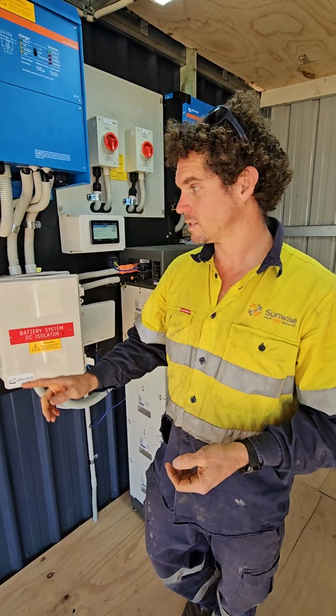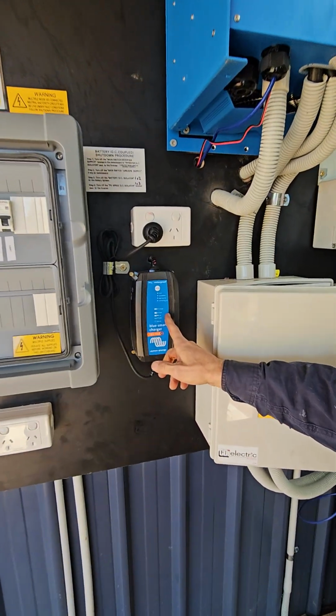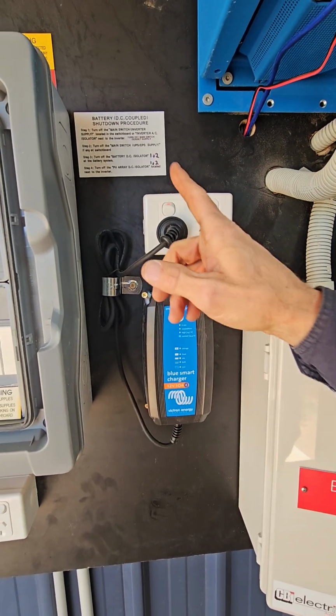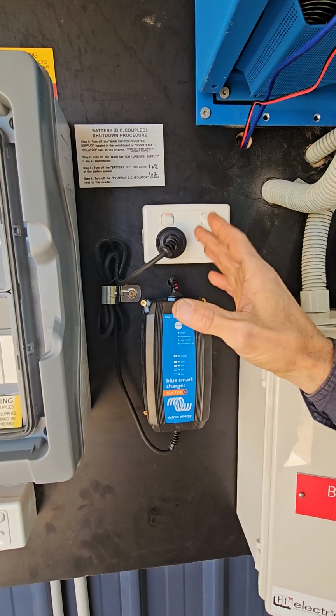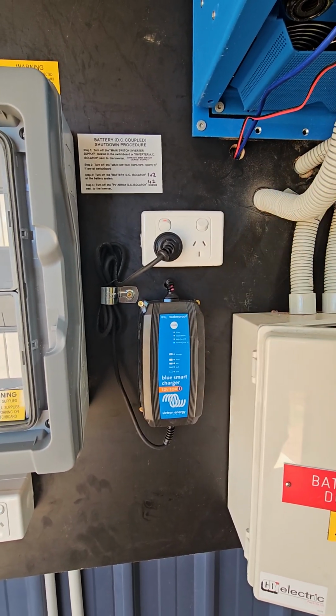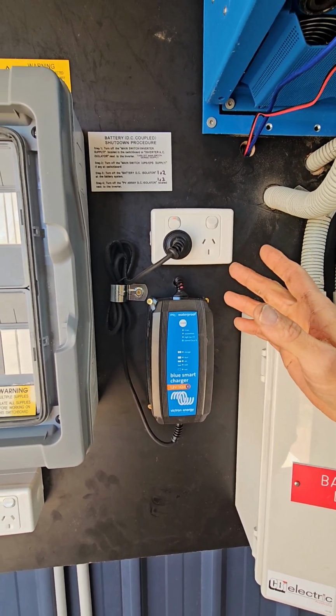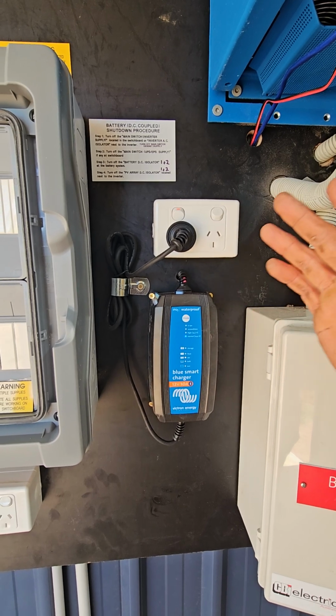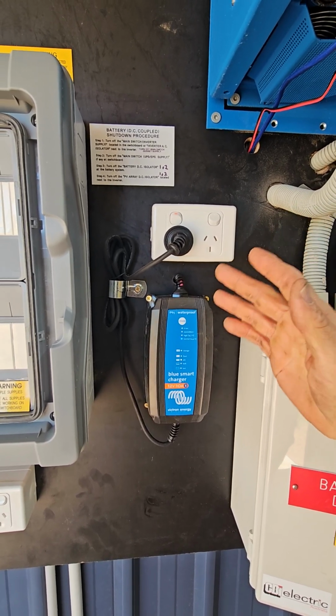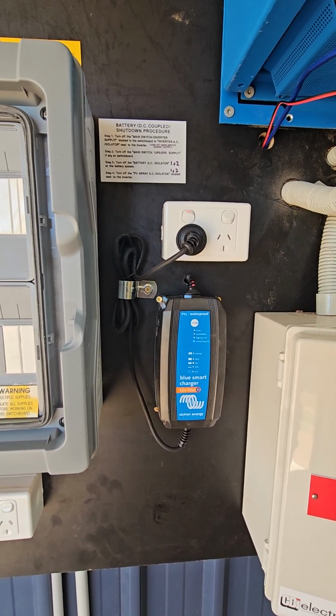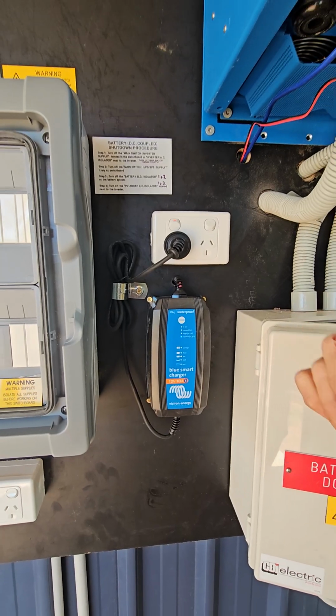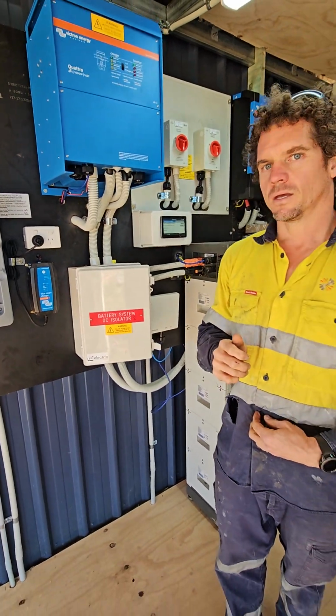There's only one other part of the system I mentioned when I was at the generator, which is your generator battery charger. So here you have your generator battery charger, plugged into this power point here. Leave that plugged in, leave that turned on. Your battery will go flat and your generator won't start if you turn that off. Basically the generator needs a constant little trickle charge to make sure it can stay in auto with the screen on for the operation of the system.